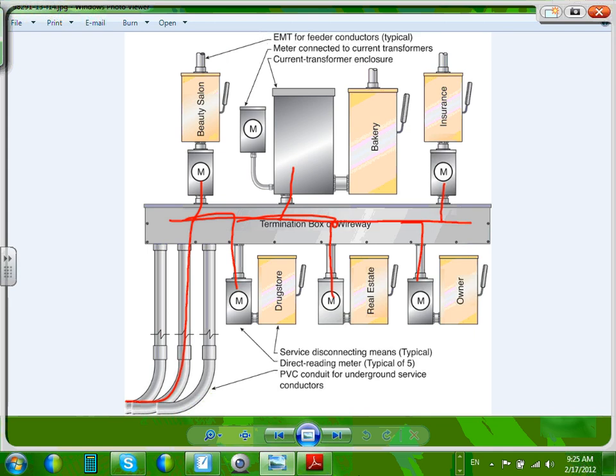Now you can do it this way, or in a case like this, can you guys see each one of them has its own meter because they're different tenants? You do this one in a strip mall. The strip mall has different tenants, right? And when you feed every tenant, the easiest way to do it is to bring the feeder to a gutter like this, outdoors, and literally tap into the feeder and go to every area. And of course, you have to land in the meter. Out of the meter, you're going to go to the first disconnect and the second, and so forth. Any comments about this? This is probably the cheapest way of doing a strip mall with multiple different occupants.